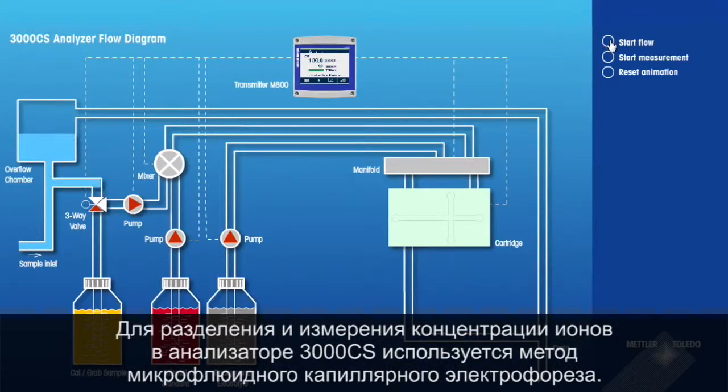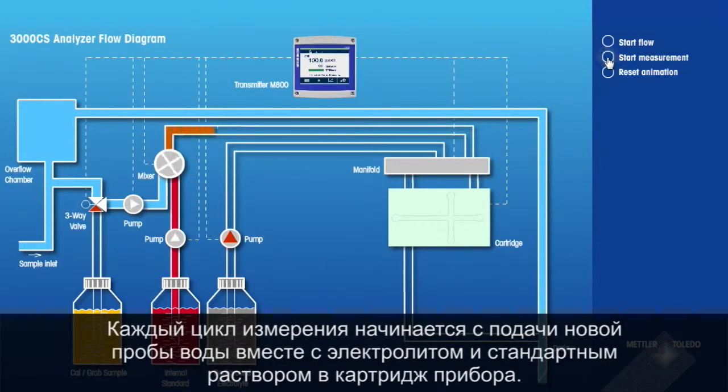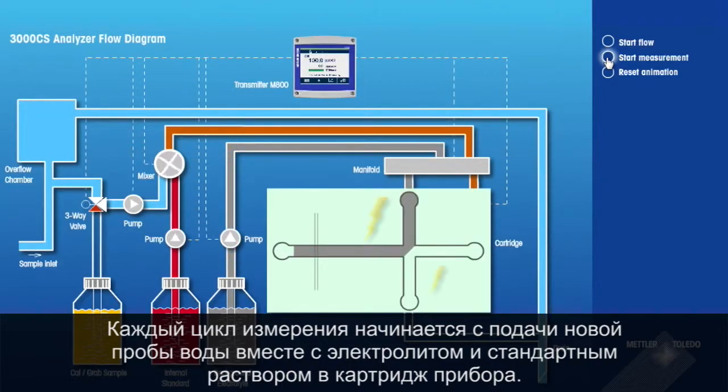The 3000 CS Analyzer uses microfluidic capillary electrophoresis, an ionic separation technology, to isolate and measure ionic contaminant levels. At the start of each measurement cycle, a fresh water sample is loaded, along with associated electrolytes and standards, onto a cartridge in the unit.